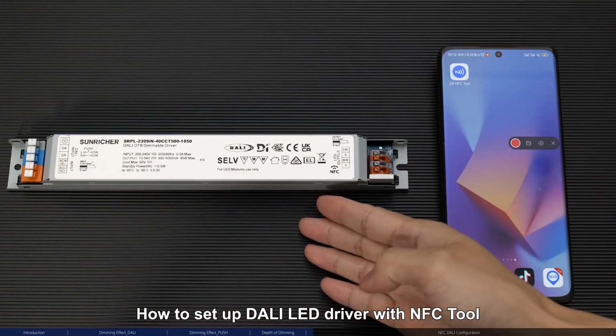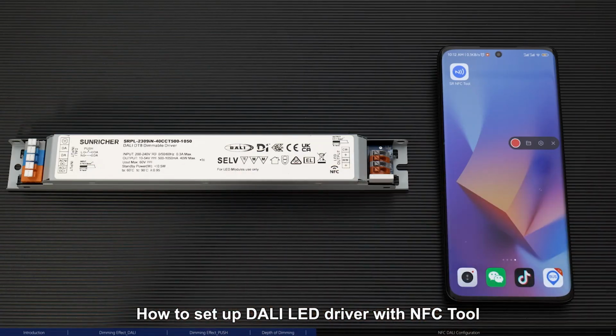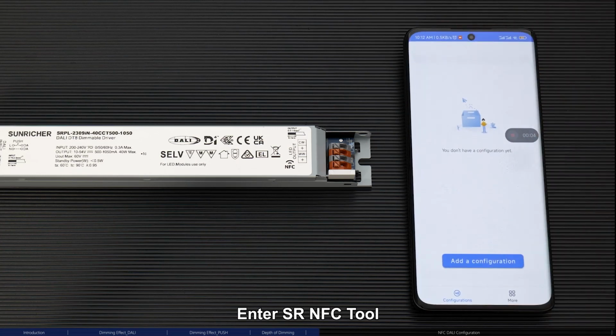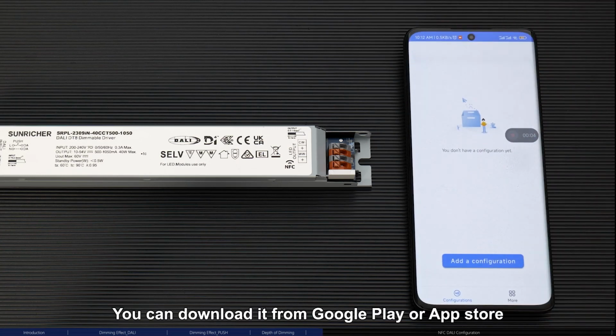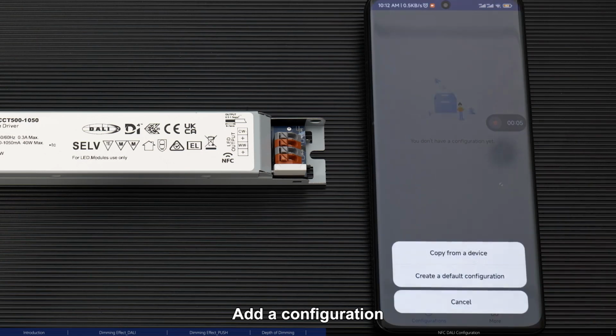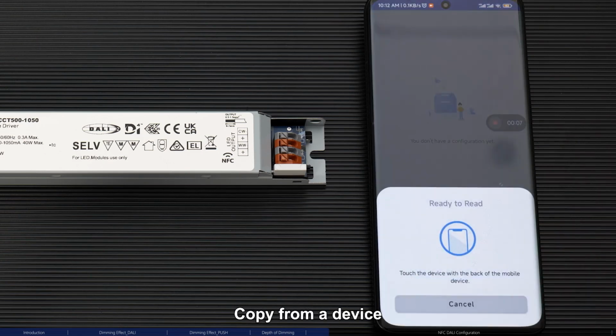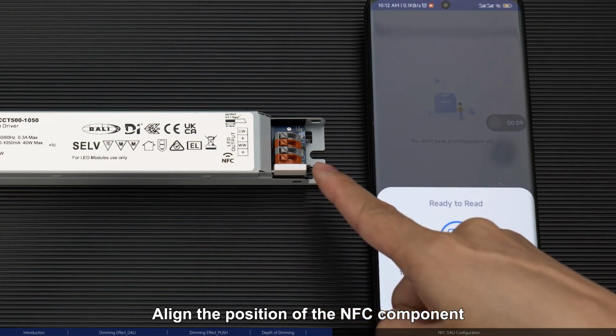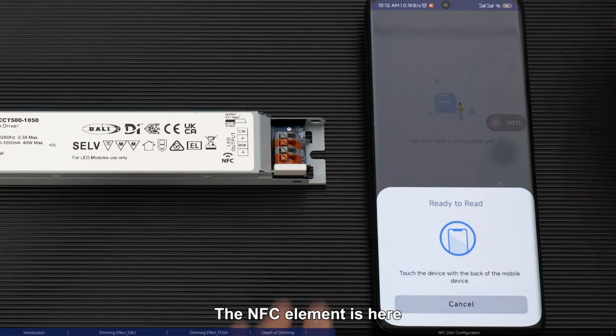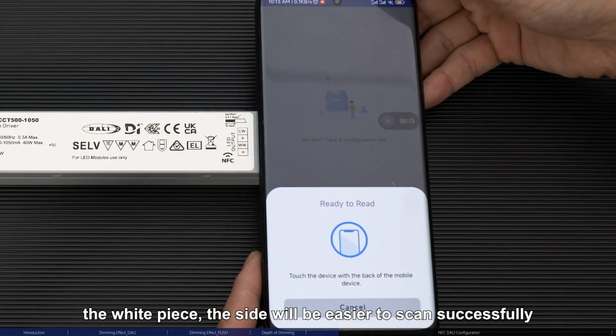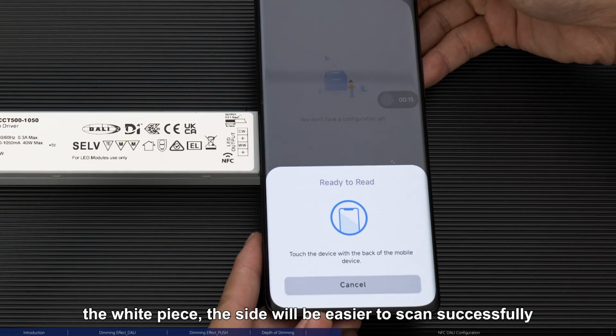How to set up DALI LED driver with NFC tool. Enter SR NFC tool. You can download it from Google Play or App Store. Add a configuration. Copy from a device. Align the position of the NFC component. The NFC element is here, the white piece. The side will be easier to scan successfully.